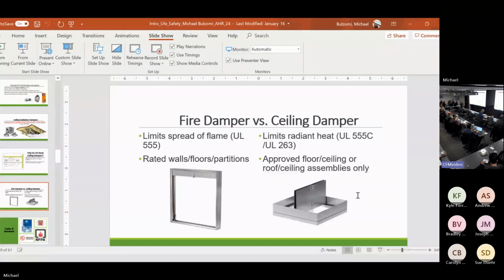Again, for my multifamily designers, say I put a furnace in a closet, sheetrock it in. I duct up through the ceiling into my trusses, and then I drop all my registers, right? That penetration needs to be protected, and then all my ceiling penetrations on the register. Those register penetrations, 10x8, 12x6, it's all standard stuff. It's this penetration coming off the unit. I got an 1800 CFM unit feeding an apartment, 2 bedroom, blah, blah, blah. Maybe I have an 18 by 18 discharge on that furnace. Maybe I have a 20 by 20 discharge.